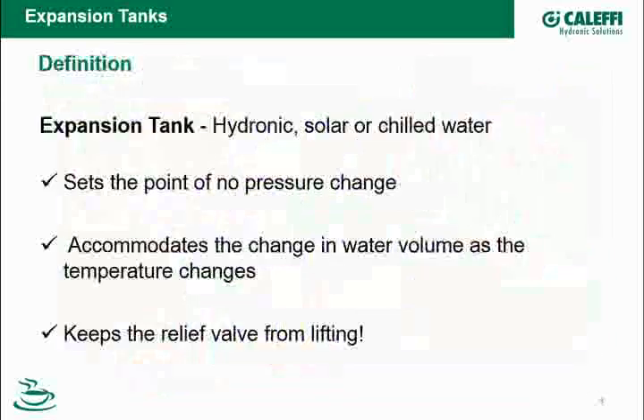One of the things our industry has done very well is train on the concept of the point of no pressure change. If I look at what the expansion tank is doing, one of the things it does is set the point of no pressure change. We're going to talk about this through the presentation. This is really the relationship between the expansion tank and the system circulators. By definition, the expansion tank is there for the expansion of the water in the system.